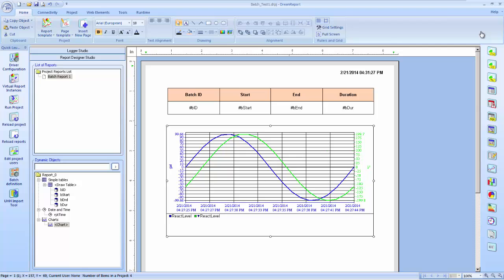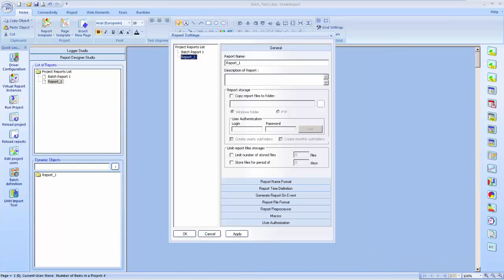In that case, what we're going to do is in our HMI or app server or the PLC, hold a bit high or set that value to 1 for the duration of the batch, and then reset it to 0 through some either push button or some logic that says that the batch has ended. There might be again a changeover, next batch ID is assigned, and then a short while later somebody presses the start button, again batch status goes to 1 and the process is repeated. So the key to this is identifying or capturing the start time when that batch status bit goes to 1 and capturing the timestamp when it goes to 0, and then that of course indicates the end of the batch.